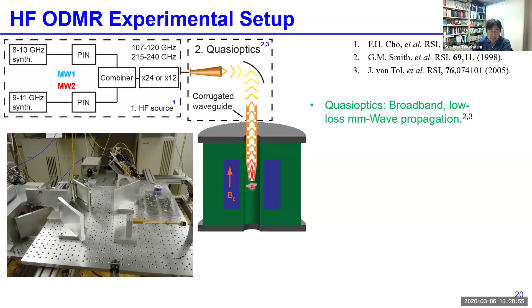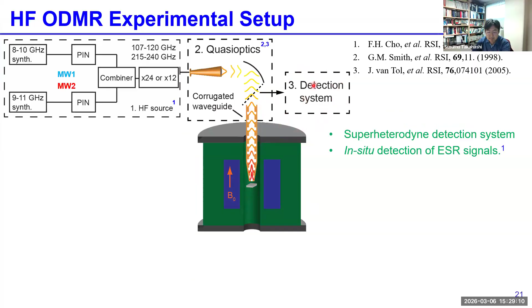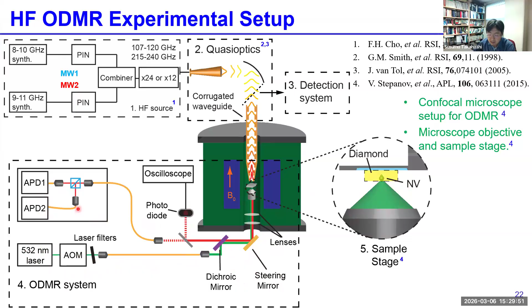We also have this microwave detection system for conventional ESR or EPR measurement. So in addition to ODMR, we can perform EPR, which is convenient to test the sample. For the ODMR detection, we have the laser access and the fluorescence detection paths coming from the bottom of the magnet. We use solid state lasers and an AOM, and a steering mirror for imaging of the diamond, using a lens and an objective. The laser is focused down to the diamond surface, and the fluorescence is detected by the same objective and then goes to detectors based on avalanche photodiodes.